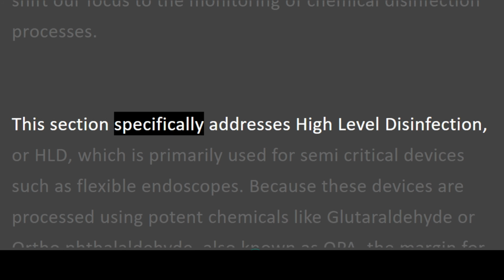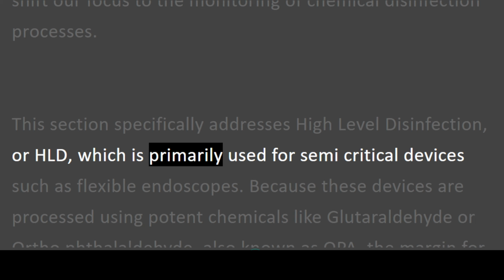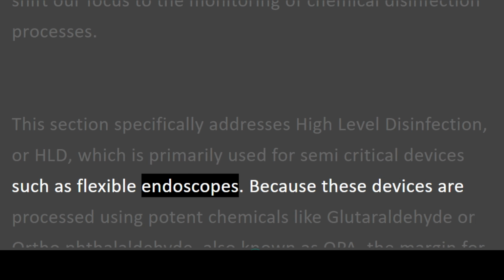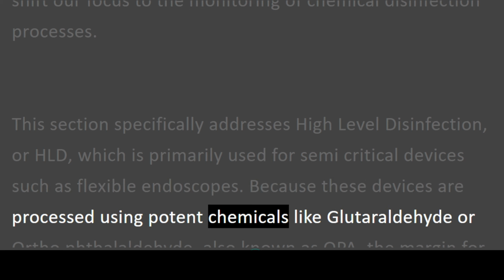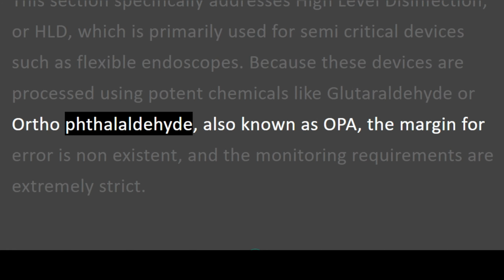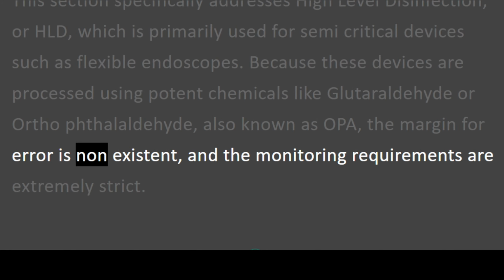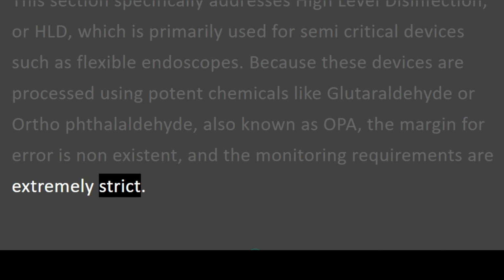This section specifically addresses high-level disinfection, or HLD, which is primarily used for semi-critical devices such as flexible endoscopes. Because these devices are processed using potent chemicals like glutaraldehyde or orthophthalaldehyde, also known as OPA, the margin for error is non-existent, and the monitoring requirements are extremely strict.